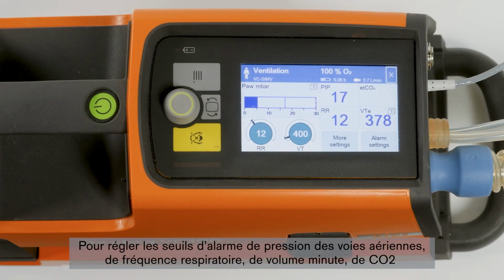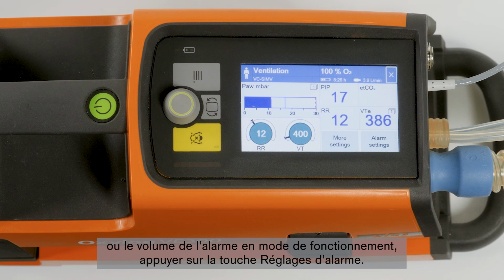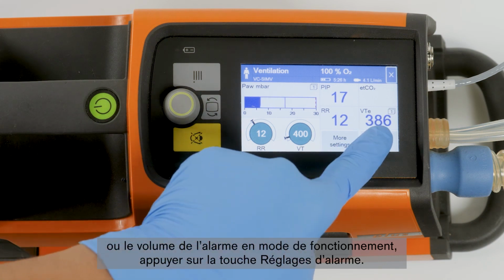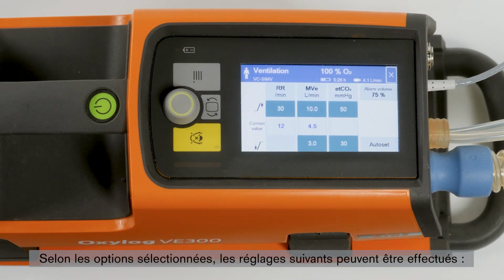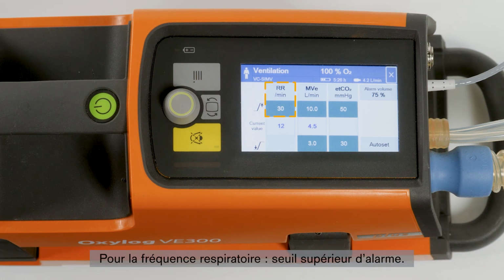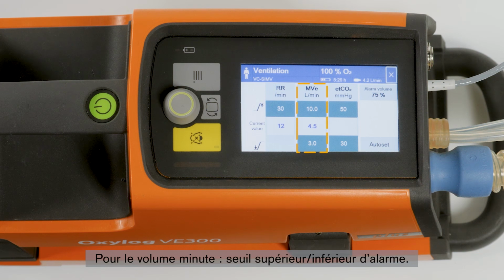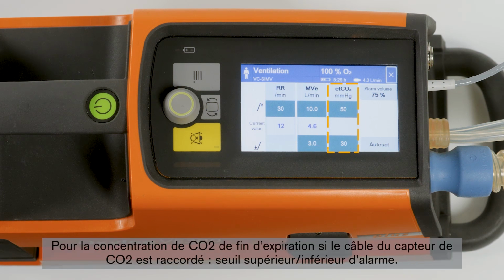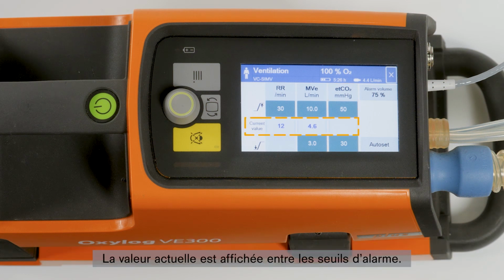To set the alarm limits for airway pressure, respiratory rate, minute volume, CO2 or alarm volume in operation mode, touch the Alarm Settings button. Depending on the selected options, the following settings can be made. For the respiratory rate, the upper alarm limit. For the minute volume, the upper alarm limit and lower alarm limit. For the end tidal CO2 concentration, if the CO2 sensor cable is connected, the upper and lower alarm limit. The current value is displayed between the alarm limits.